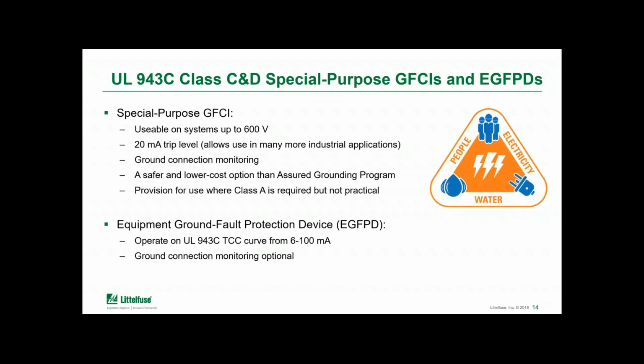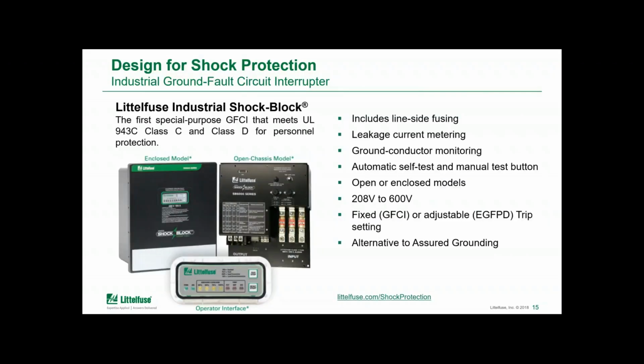Now, another type of device mentioned in that standard is the Equipment Ground Fault Protection Device, with the acronym EGFPD. That is quite a mouthful, but the name makes it clear that it's not the same personnel protection as the fixed GFCI. That's really just because it allows adjustment of the trip level up to 100 milliamps. Again, it does operate on the same UL 943 time-current curve, which will provide a good degree of protection for personnel even up to the 100 milliamp level, and again with an even faster trip. But only devices that have a fixed trip level at that 20 milliamp number will qualify to be called a GFCI. So here is an example of a special purpose GFCI and EGFPD that's available on the market today.